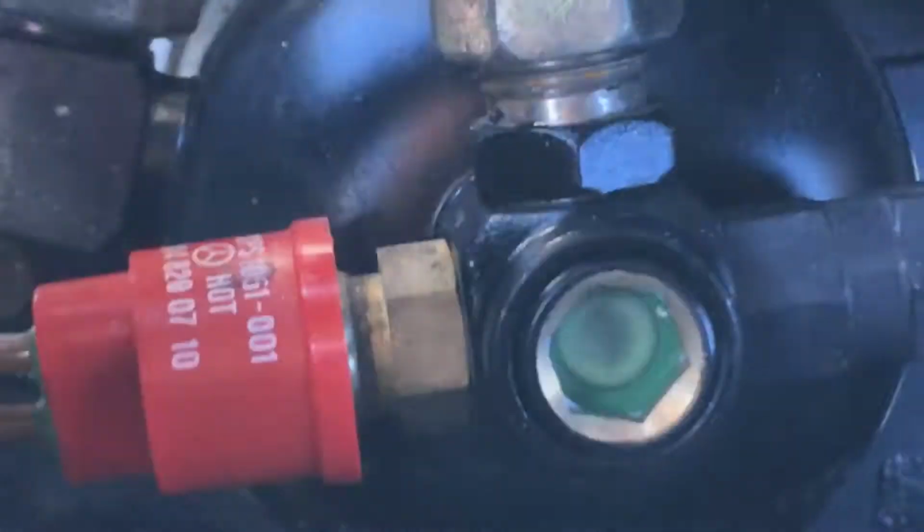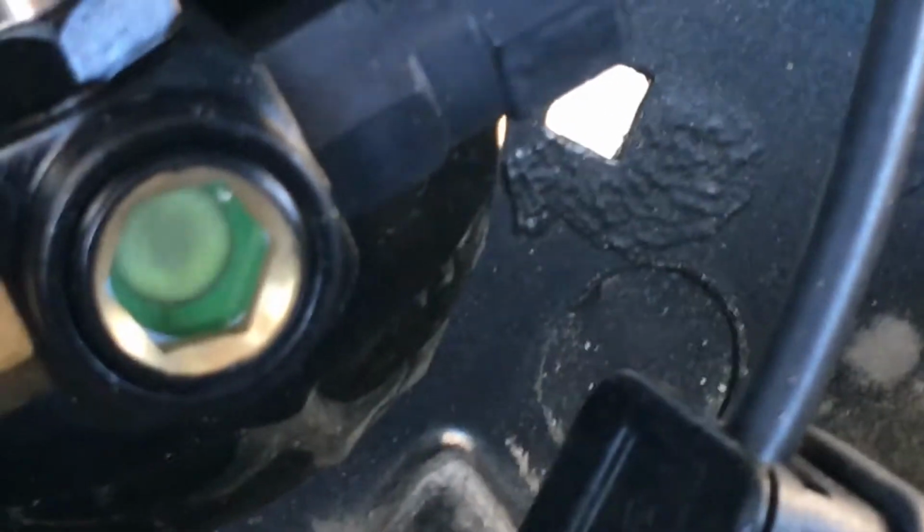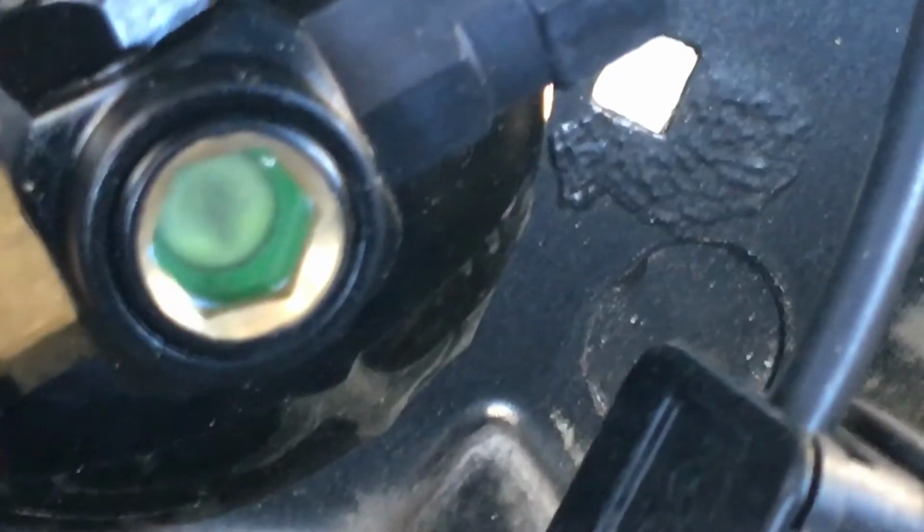But another thing, this is when a sight glass does work, when you really are this low. Let's see if I can zero in on the sight glass. Come on, get down there, zero in. Damn, I can't zero in. I'm sorry, guys, my focus does not want to focus. A little bit, you can see it trying to focus down there, and you can see all the bubbles. It's not even bubbles, it's basically almost empty. There we go. It likes that. Okay, so you see that sight glass?